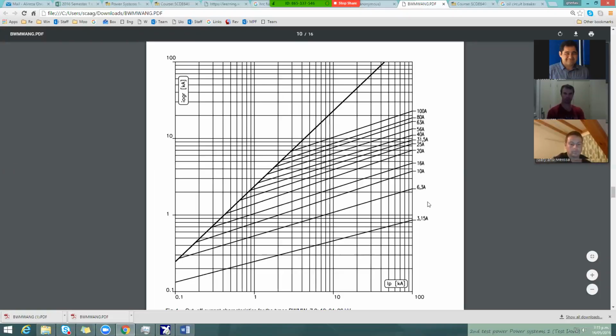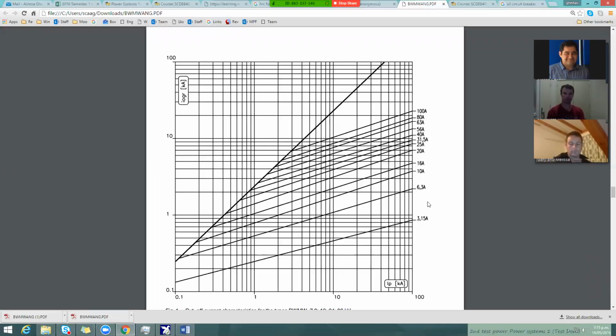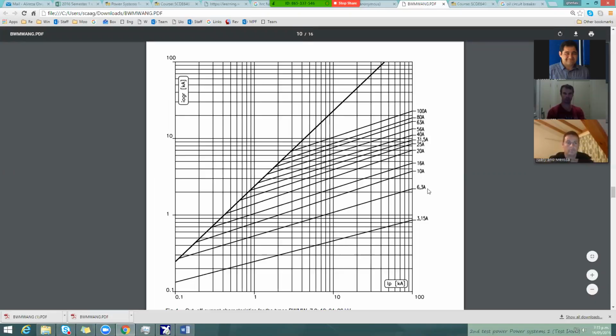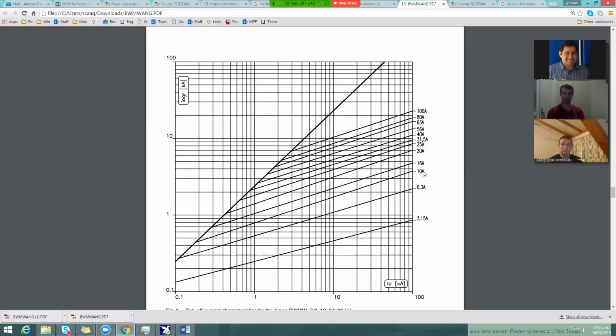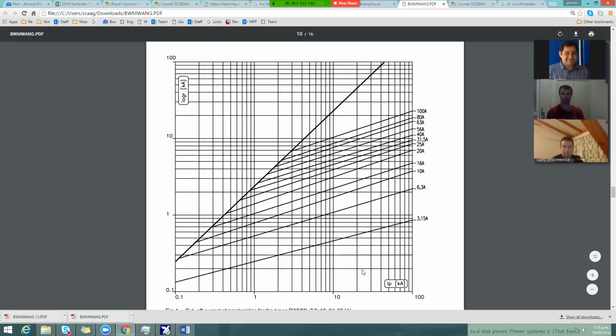So what do we need to do if we wanted to use this? One, we need to make sure the rating is working for our situation. So we need to make sure that, for example, if our current is 10 amp - actually if you look at this, you can see it is not going to interrupt 10 amp. But if your current is more than 10 amp, you should never use this fuse, because this fuse is only rated up to a specific value.